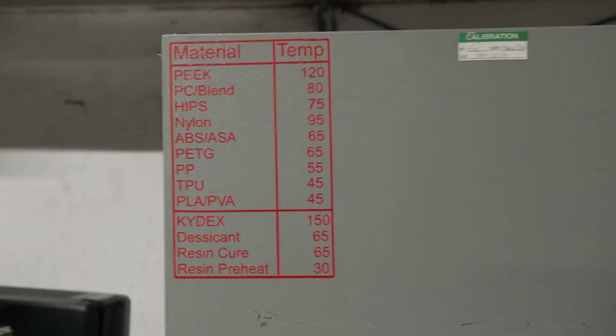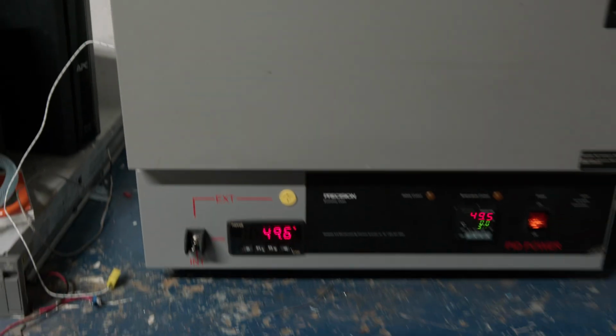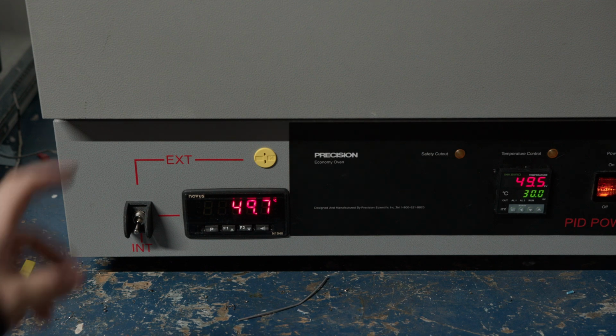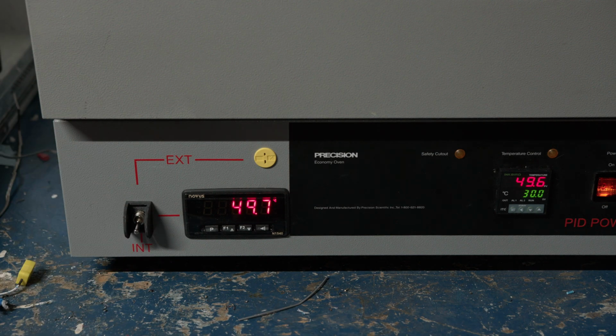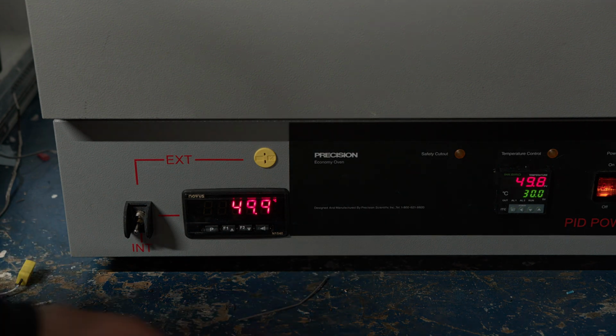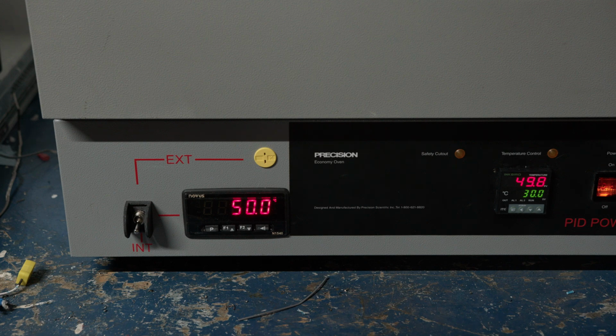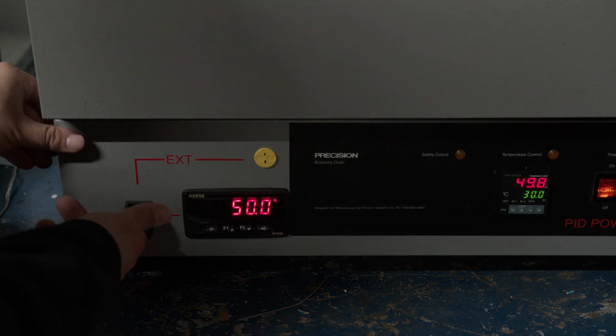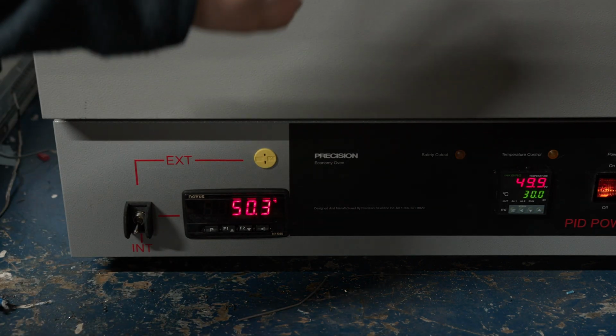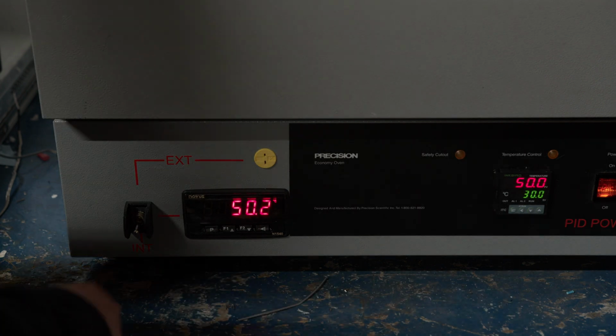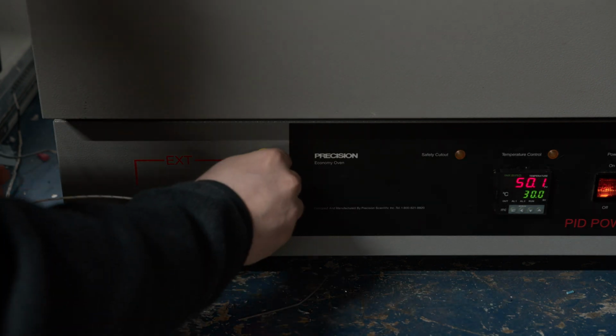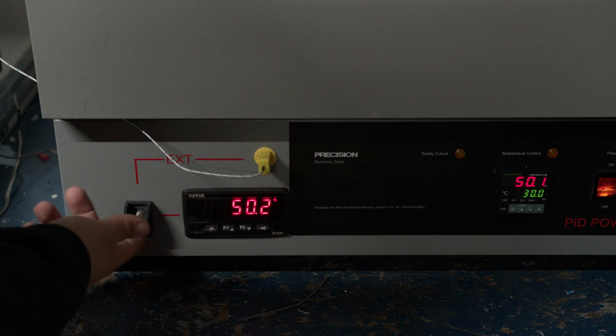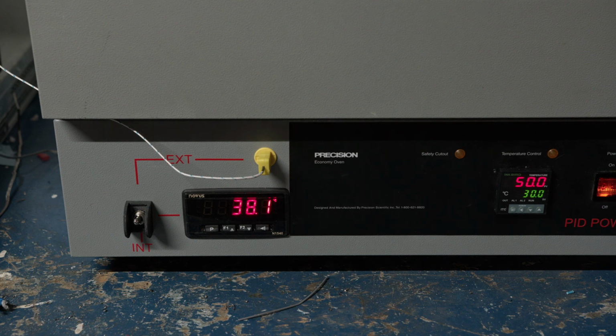So I've got a little temperature chart for materials right there. And then I've got the Novus N1050 display still there. I figured instead of 3D printing a little gap adjustment thing, I ordered a K-type thermocouple socket, a couple small and a couple full-size ones, and I thought it would be good to be able to switch to another thermocouple. So basically you can have your internal temperature, which is one of the two thermocouples up top in the lab oven, or if you want to measure a specific spot, you can plug in a probe, switch to the external input, and you can monitor the temperature like that.